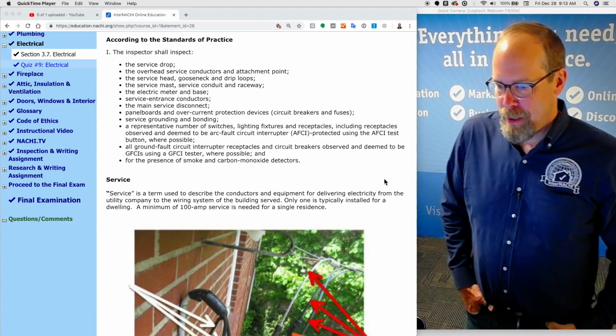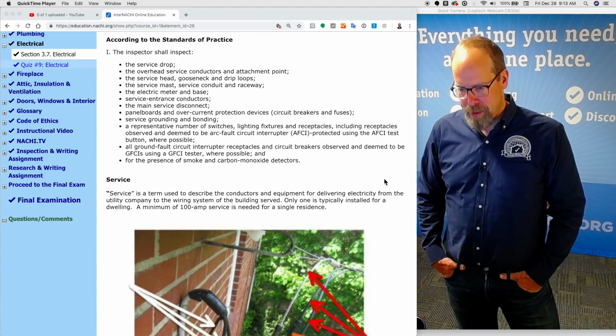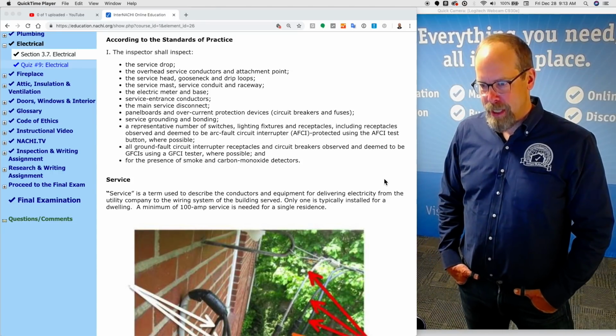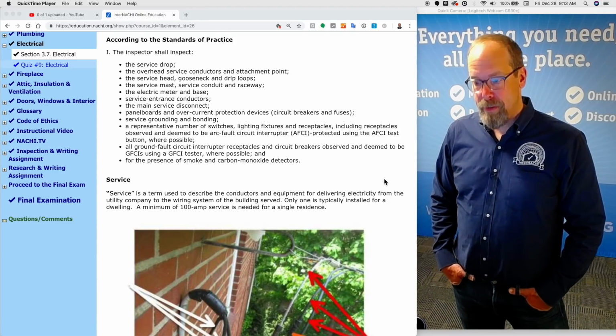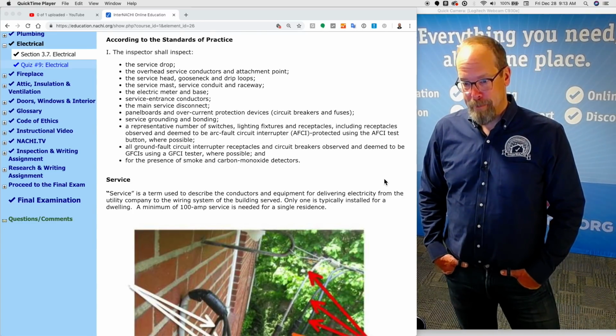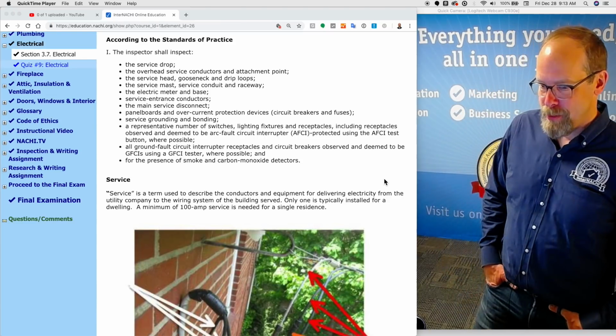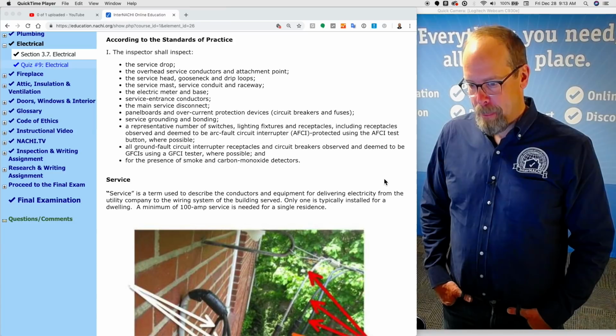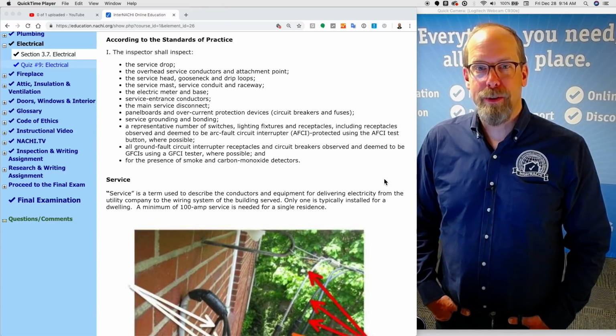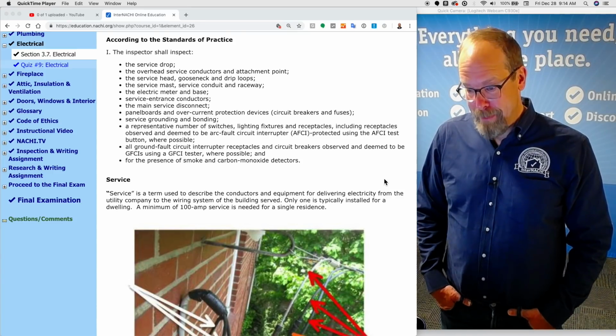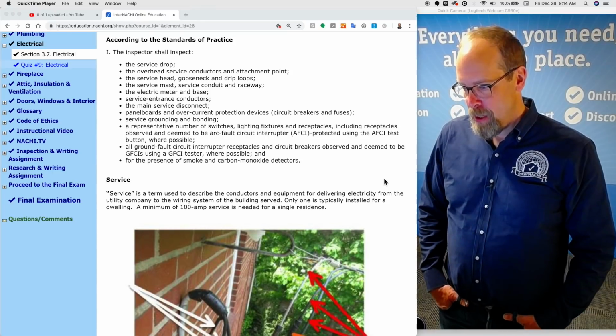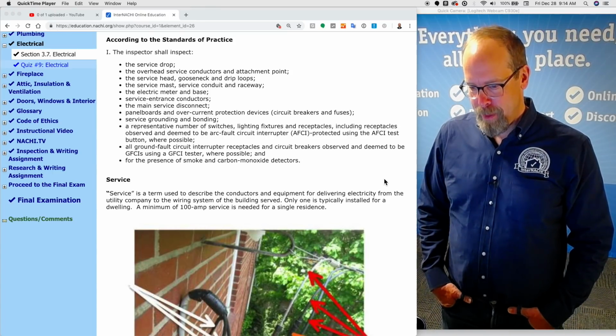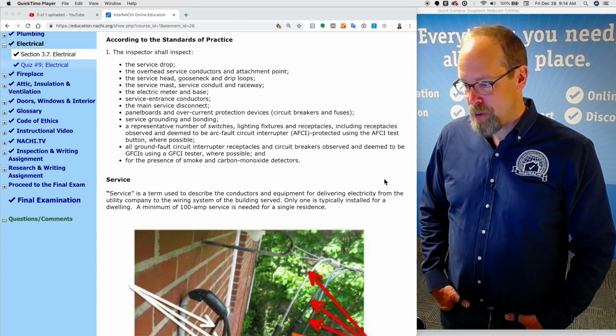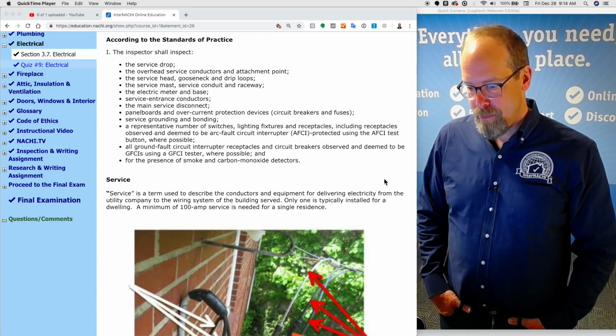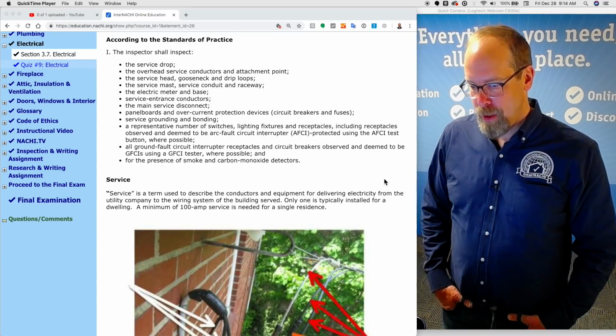There's a lot. The inspectors shall inspect the service drop, the overhead service conductors and attachment point, the service head, gooseneck, and drip loops, the service mast, service conduit and raceway, the electrical meter and base, service entrance conductors, the main service disconnect, panel boards and overcurrent protection devices, that's circuit breakers or fuses, service grounding, bonding, a representative number of switches, light fixtures, receptacles, including those observed and deemed to be arc fault circuit interrupters, AFCIs, using the AFCI test button where possible, and all ground fault circuit interrupter receptacles and circuit breakers observed and deemed to be GFCIs, using a GFCI tester where possible, and for the presence of smoke and carbon monoxide detectors.